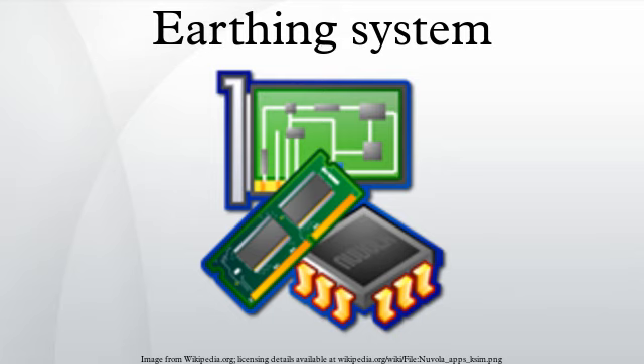In TN-S and TT systems, the consumer has a low-noise connection to earth, which does not suffer from the voltage that appears on the neutral conductor as a result of the return currents and the impedance of that conductor. This is of particular importance with some types of telecommunication and measurement equipment. In TT systems, each consumer has its own connection to earth, and will not notice any currents that may be caused by other consumers on a shared PE line.